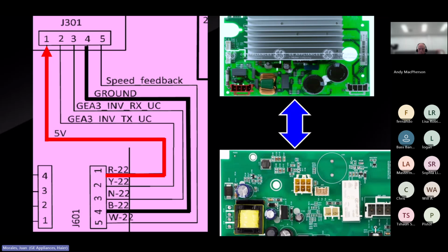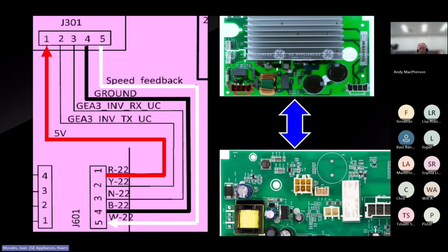But there's another very important voltage that comes from the inverter board back to the main, and that's your speed feedback. That's a voltage you cannot measure with a meter — there's just no way, because it won't give you anything consistent. It'll give you something, but the numbers are just going to be jumping around on your meter, so there's no way for you to determine it.